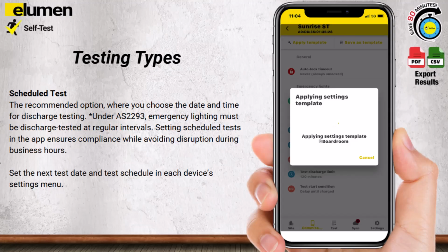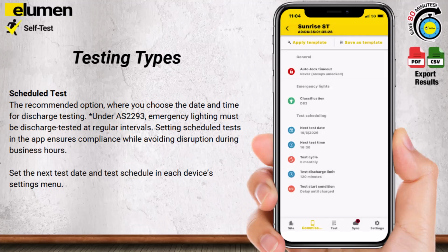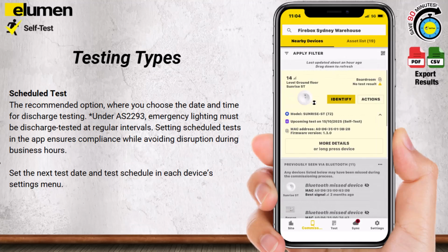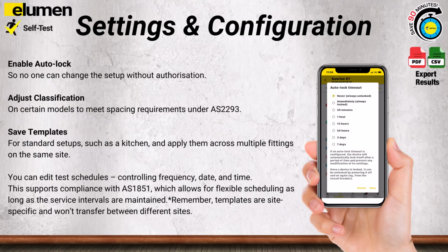The best way to do this is by using templates. Templates allow you to apply a standard configuration, such as 6 monthly tests at midnight, across all devices in a zone or building. This keeps the site consistent, simplifies reporting, and ensures all fittings remain compliant to the same schedule.